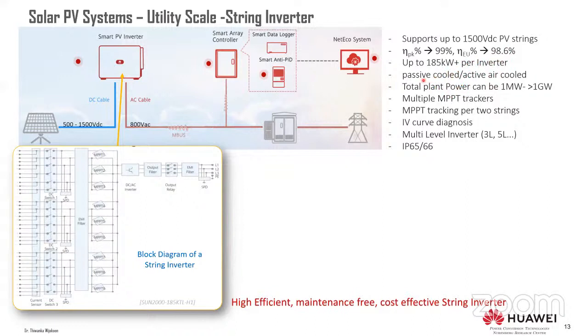One of the key points I will highlight later is maintenance. These kinds of inverters don't have active cooling. You typically use passive cooling, mainly because you want to avoid maintenance during the lifetime, which is typically 25 years. And of course, as I mentioned before, these kinds of string inverters can be used to go up to several gigawatts of power conversion, right?